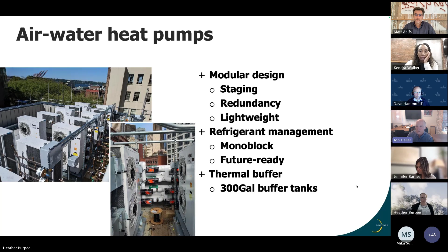They're what we call a monoblock design, which means that there's no field connections of refrigerant. The whole heat pump refrigerant system is contained in a factory delivered unit, so it really reduces the chance of refrigerant leakage and minimizes the amount of refrigerant on the project. No refrigerant is inside the building. And the system also includes large thermal buffer tanks, which allow for better cycling of the heat pumps and will also allow for some demand response to turn the heat pumps off during peak demand periods.